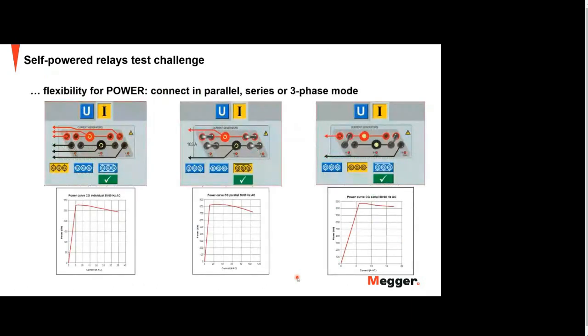But with the Sverker 900, it's possible to run in single-phase mode also with the current generator. Single-phase mode means that we connect the current generators in series or parallel. And if we do that, we increase the power three times, or we increase the current amplitude three times. So it's a summation. That's an advantage. We have very good flexibility to test. And of course, we can also run the current generator in three-phase mode and do the three-phase testing. So we have a lot of flexibility with the Sverker 900 when testing self-power relays.